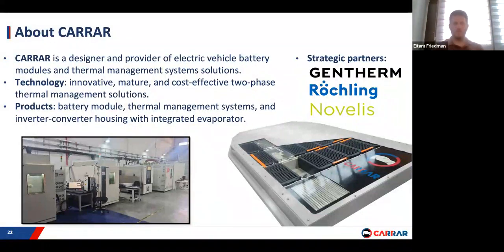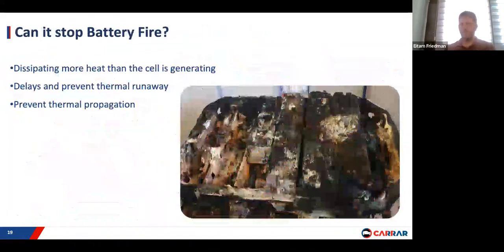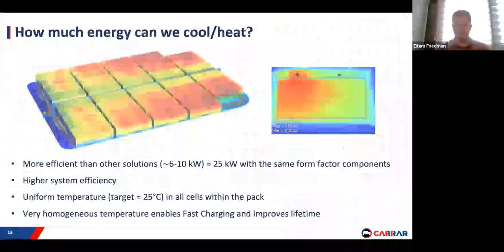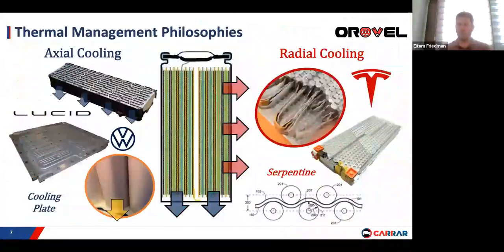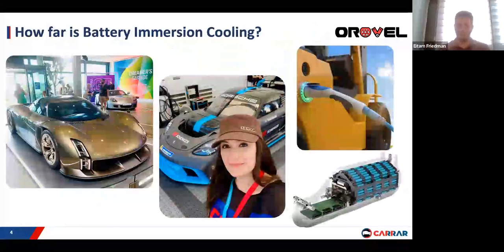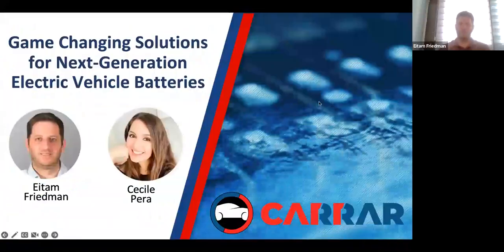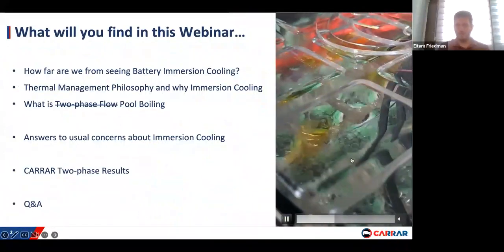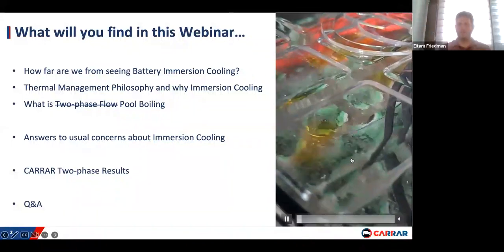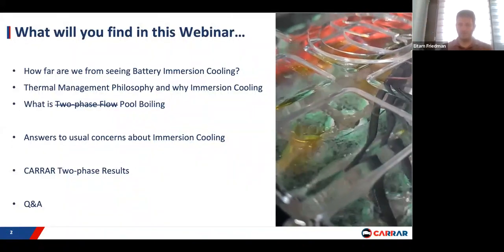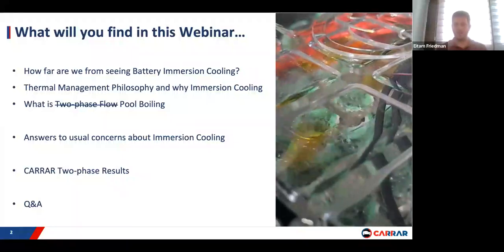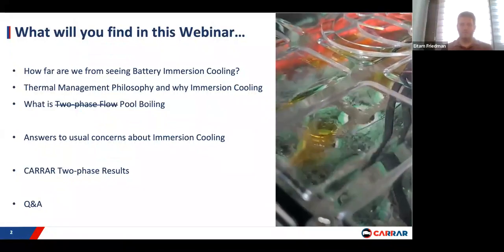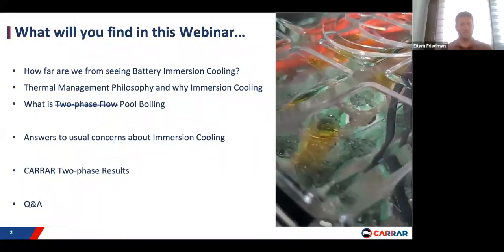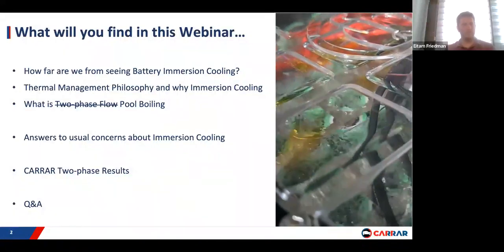On an immersion solution, we see numbers that can get up to 50 liters per pack. But because we don't need to circulate a lot of refrigerant, we don't need to have a lot of refrigerant in our reservoir, so it's not a lot of refrigerant inside. You can see here in the movie, it's the nice boiling. I hope I answered the questions. If not, you can comment.